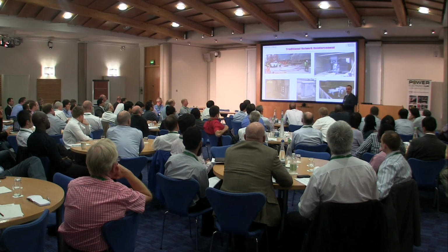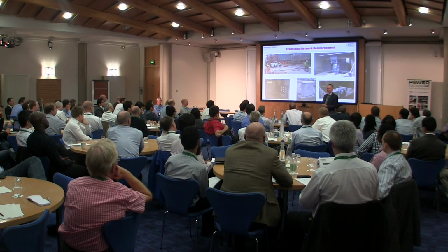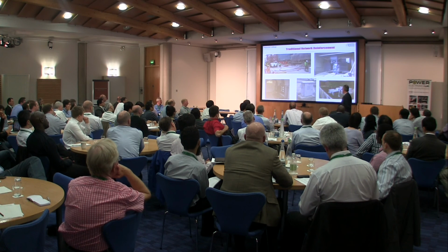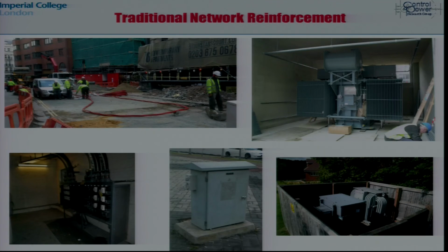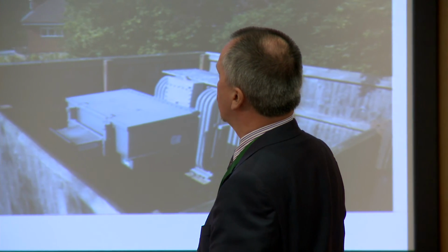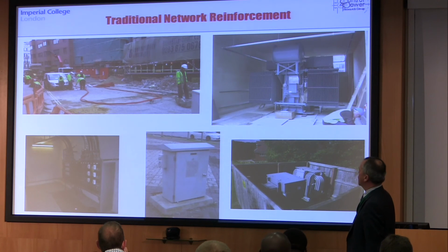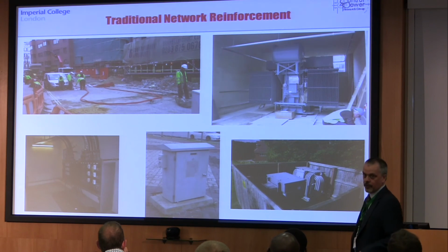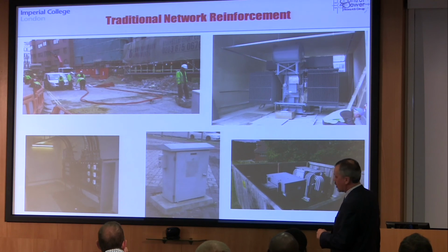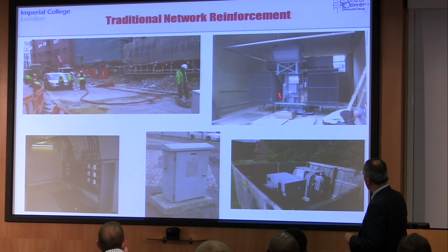Network operators' first approach to resolving these issues is traditional network reinforcement. This is reinforcing a street just off Fleet Street, which I happened to walk down recently, where building development - new office blocks or taller ones - causes growth in demand in an already dense demand center. They're laying new 11 kV feeders up and down the streets to cope, and each time a new office block goes up, a new distribution substation goes into the basement to feed the additional load.